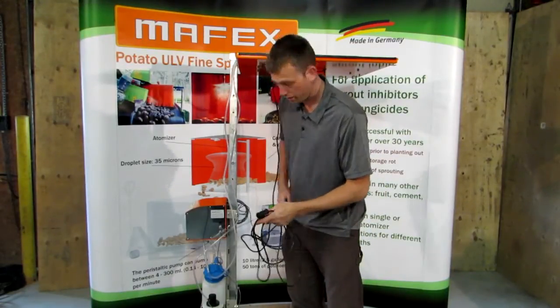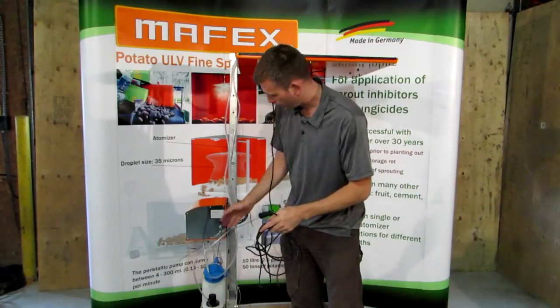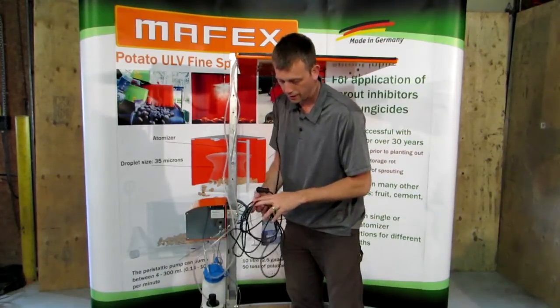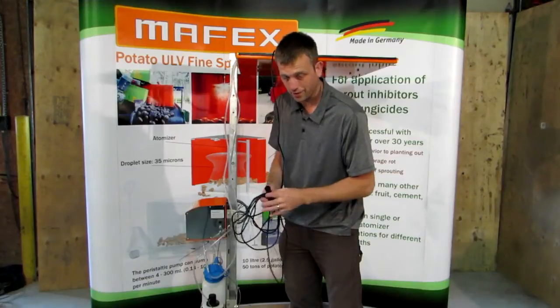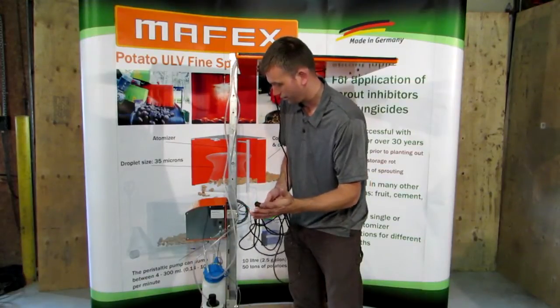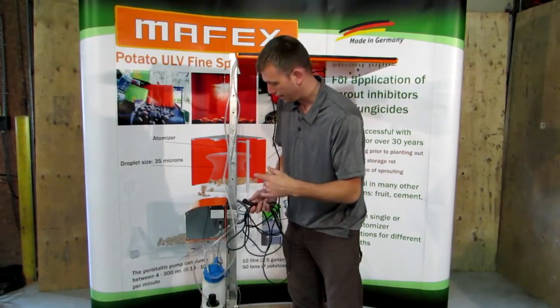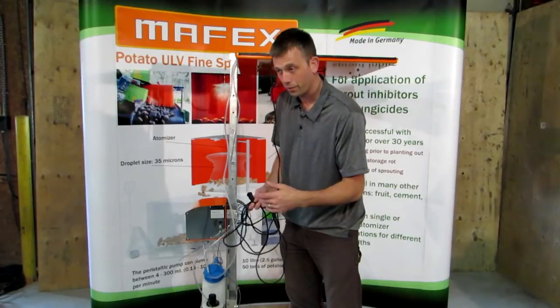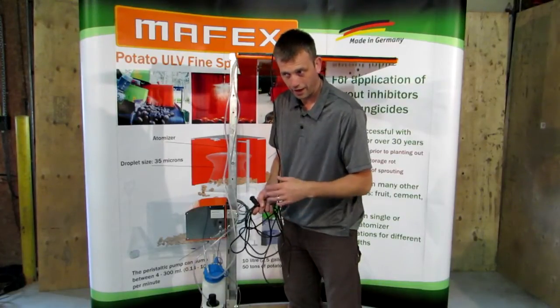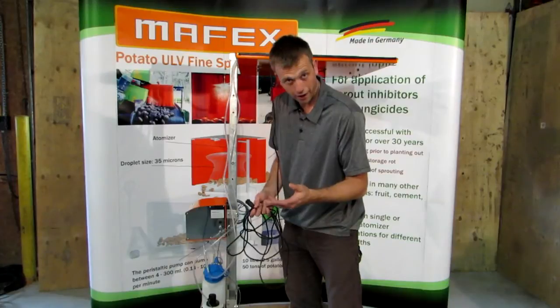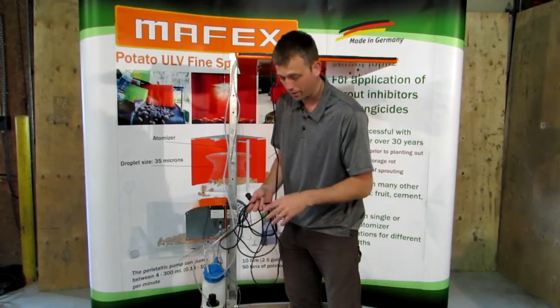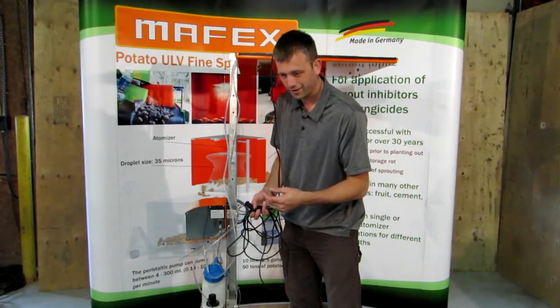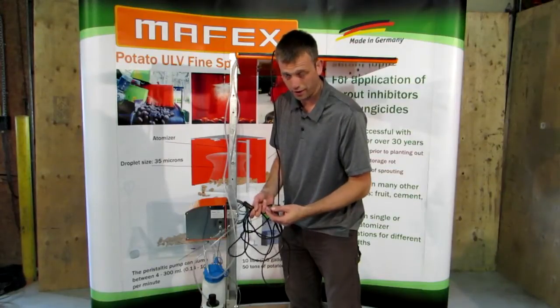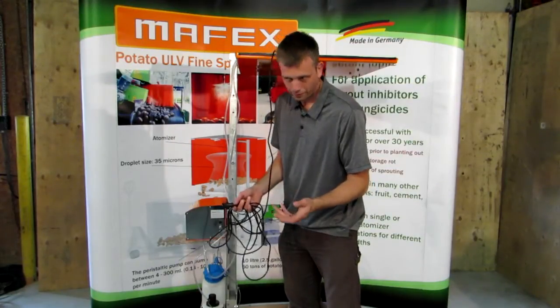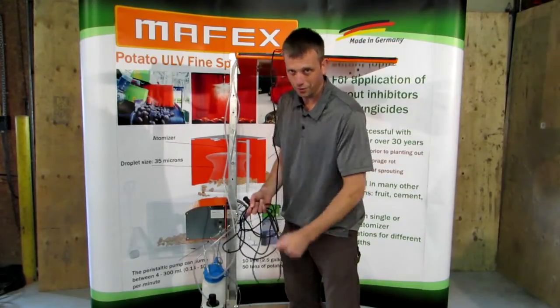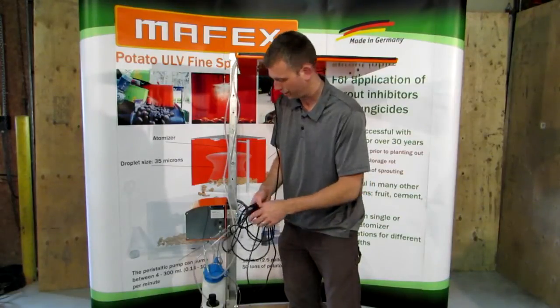There are two places to hook up atomizers underneath the pump box. If you just have a one atomizer system, you're going to use only one of them, of course. If once we start operating, we are having an alarm that's saying atomizer alarm, probably we connected to the wrong one of those two connectors. So the first thing to try in that case is to hook it up to the other connector on the bottom here.